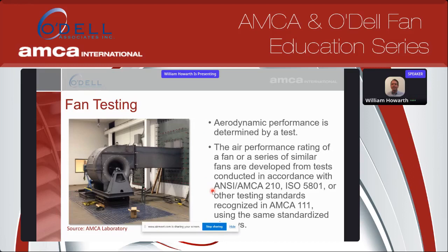AMCA operates a lab certification program where they actually send test fans out to labs so that they can check the calibration of the laboratory and make sure everybody is getting the same results. ISO 5801 is another fan testing standard, which is very similar and in technical harmony with AMCA 210.